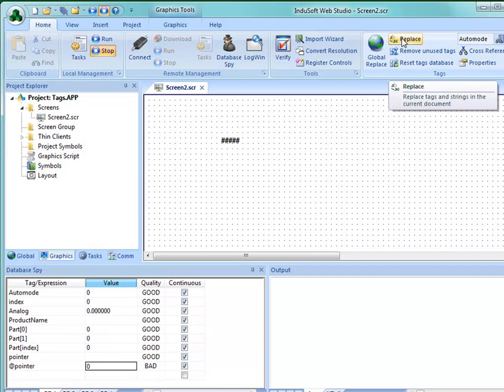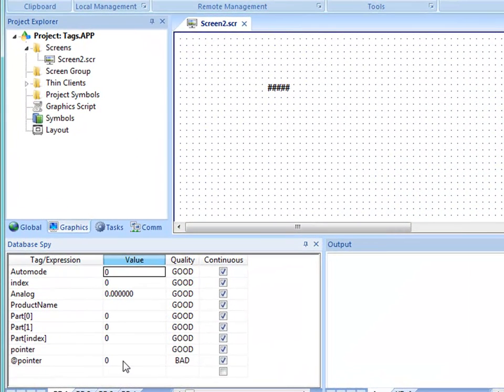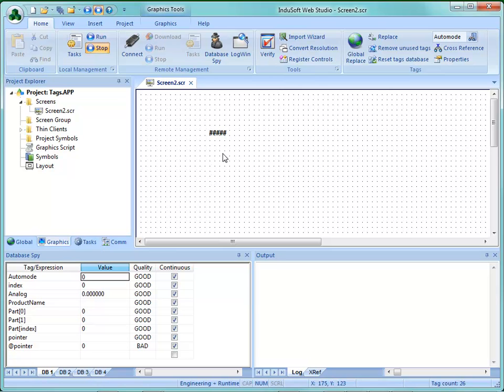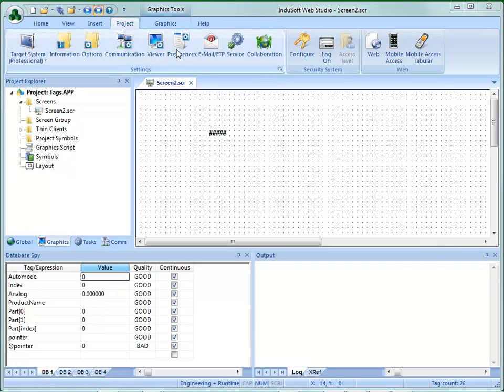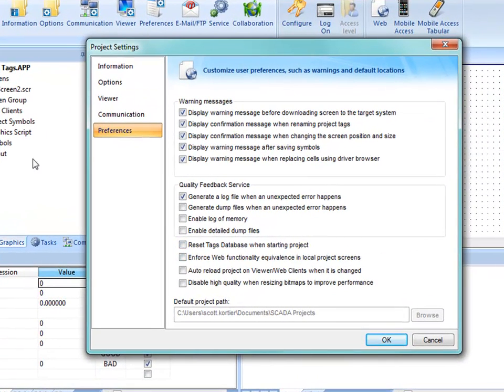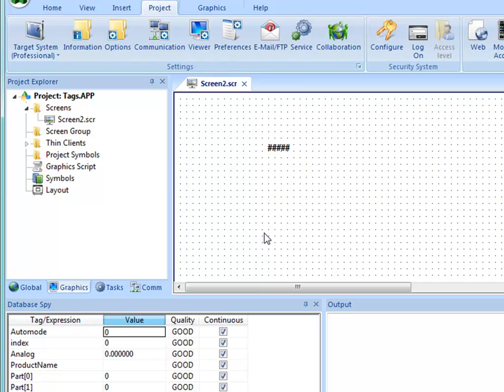Here I can do replace on an individual document, remove unused tags to clean up my database, and reset the tags database. When using InduSoft Web Studio running on a PC, tag values will persist between run and stop cycles. On Windows CE, they reset to their default values every time you rerun the project. This behavior can be changed — under Project Preferences there's a checkbox that says 'Reset Tags Database When Starting the Project', which makes desktop and server runtimes behave similar to the Windows CE embedded environment.